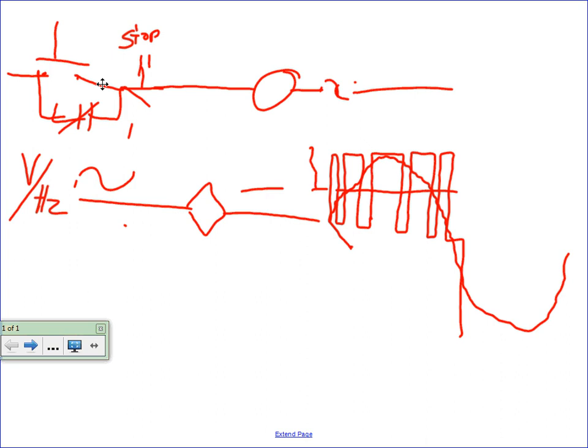And these packages, again, the open style stuff is in the digest in section 25, but what you guys would probably be using on a project is our enclosed product. The difference is, it's like a combination starter, only it's a drive or a soft start. It's got a disconnect, pilot lights, push buttons, all that stuff mounted in the enclosure. So all you have to do is hang it on the wall, hook it up to the motor, and away you go. Any questions on these products? Again, the soft start, all that does is a soft ramp up to speed and a soft ramp back to stop.